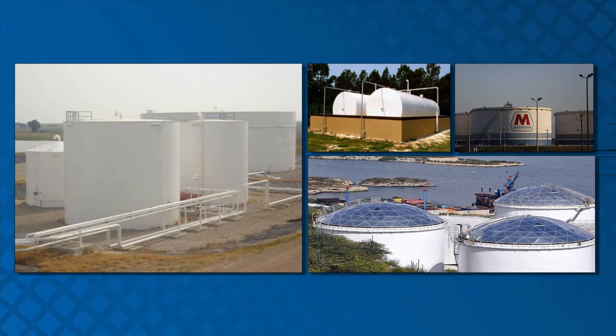The photographs in this slide depict typical installations of ethanol blended fuel storage. Both denatured and undenatured ethanol can be stored at a production facility, although the most common is denatured fuel ethanol, E95 to E98. Ethanol blended fuels found in retail fuel stations are not generally found at a production facility. There will be denaturants such as natural gasoline or unleaded gasoline stored at a production facility. Denaturants are added to ethanol through inline blending systems prior to the final product storage tanks.